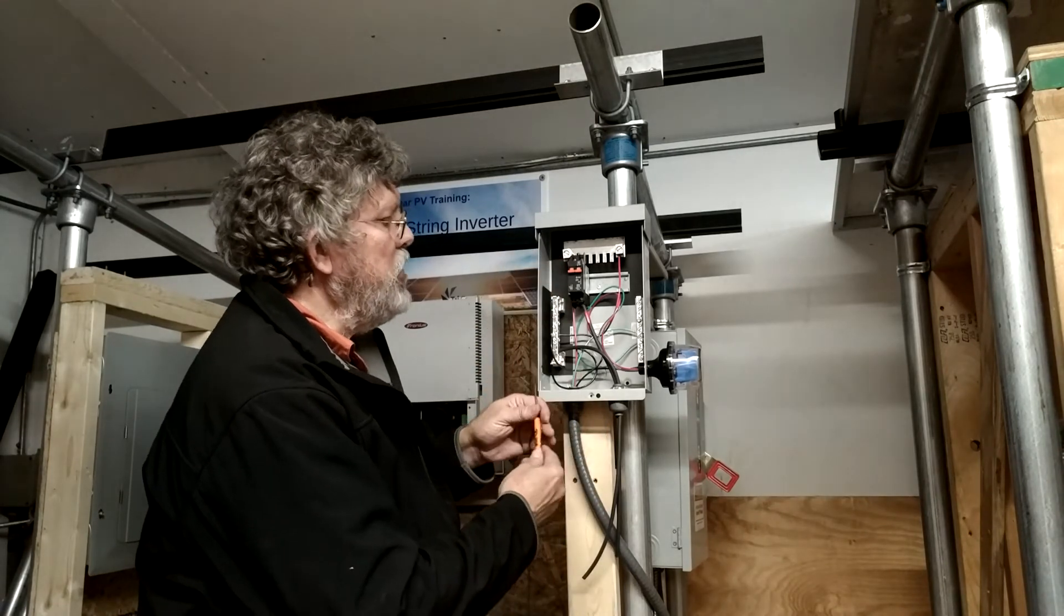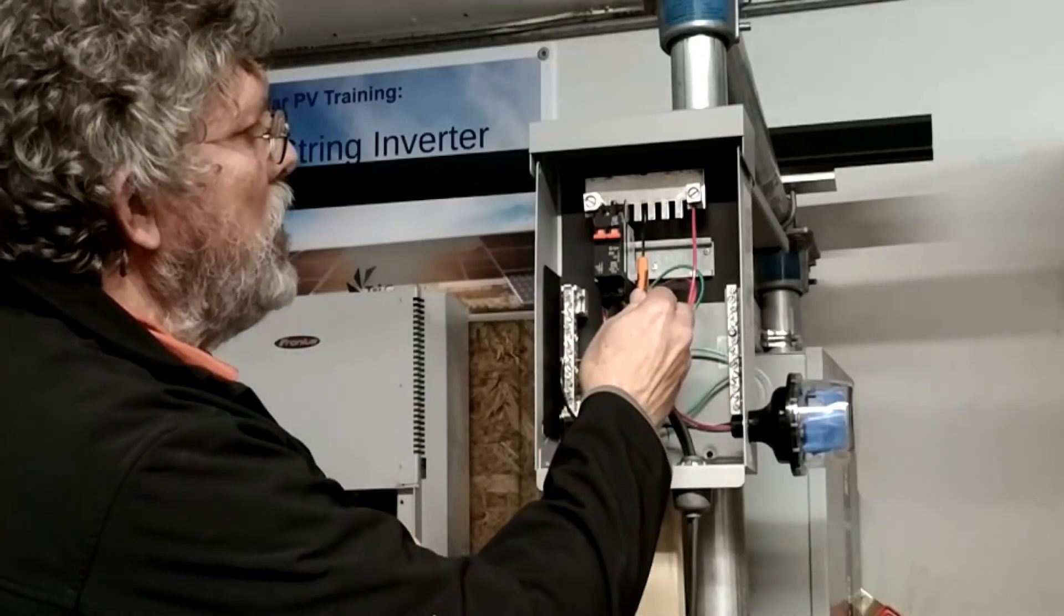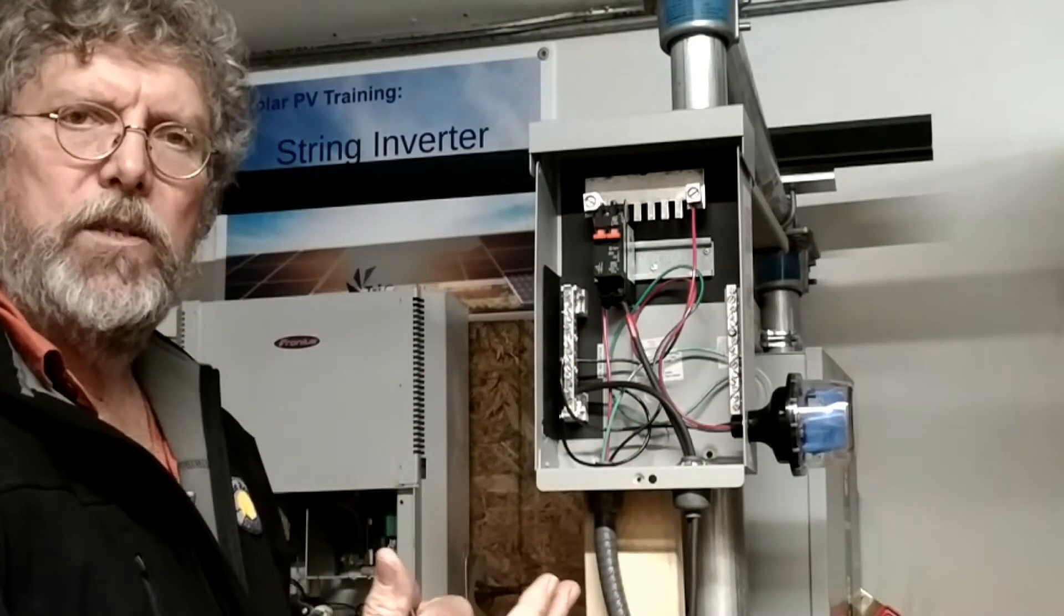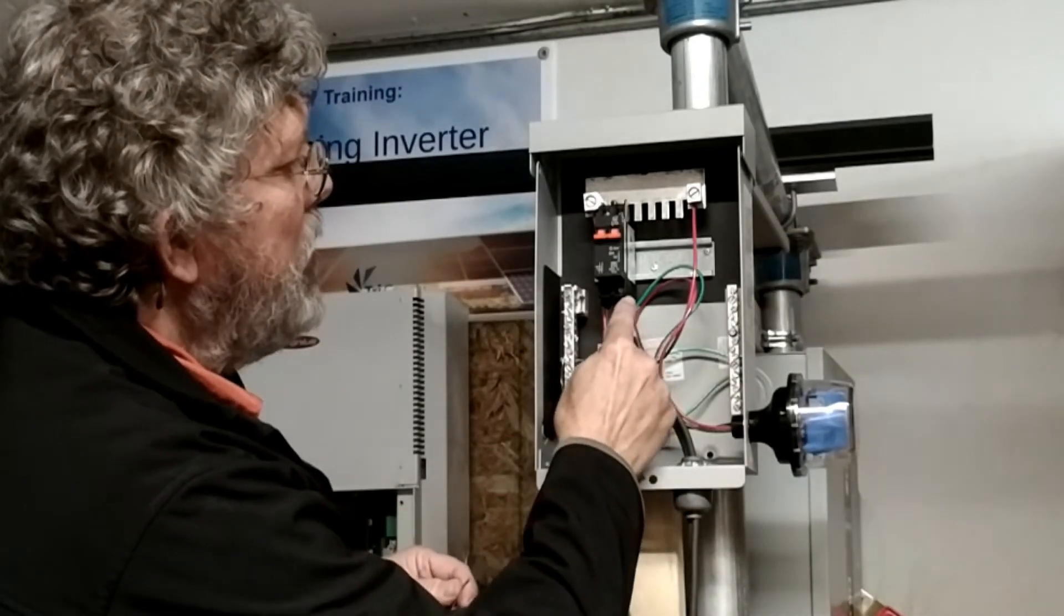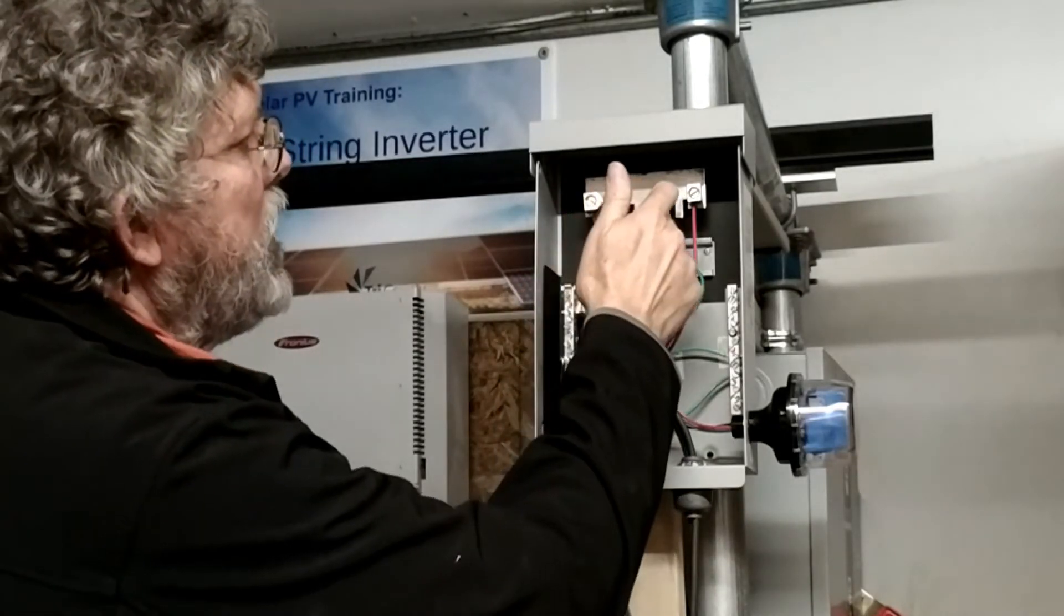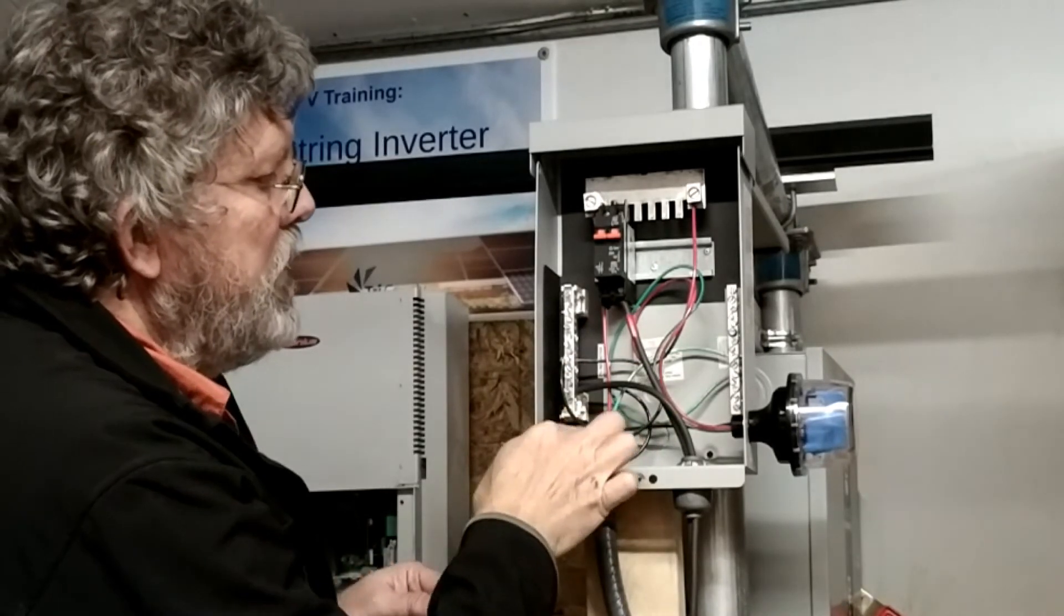So we're in this case only coming in with one string, but if we had multiple strings we could hook into multiple breakers, which is the overcurrent protection that protects each of the strings. Now here I have a positive wire coming in to the bottom. I have a positive wire which would combine all of the breakers into one circuit, which is heading out to the DC disconnect.